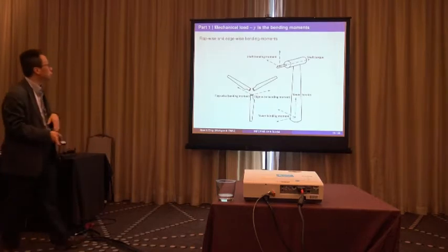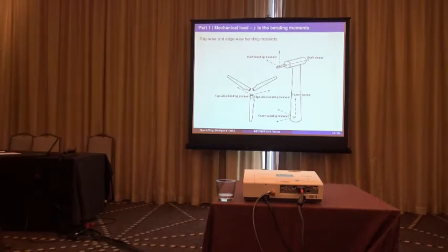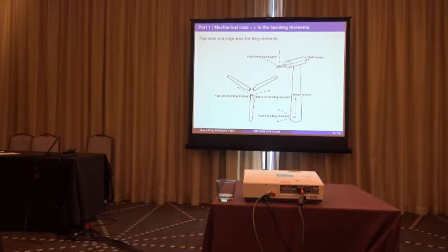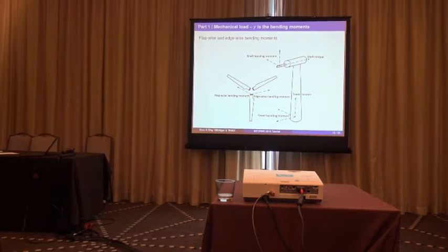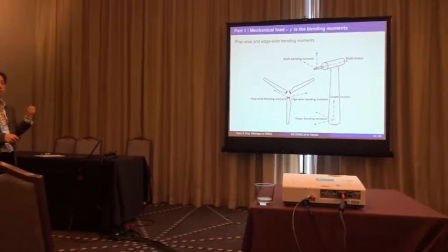Okay. But if you use Y as a bending moment, now you have a different set of data. So if we consider reliability, then we need to use the sensors that measure the wind force on the turbine systems. And particularly here, we consider the structural reliability. So on the blade side, there are several sensors that can measure the force on the blade root. And depending on the direction, they can be flapwise bending moment or edgewise bending moment. We can also consider the tip deflection on the blade tip.